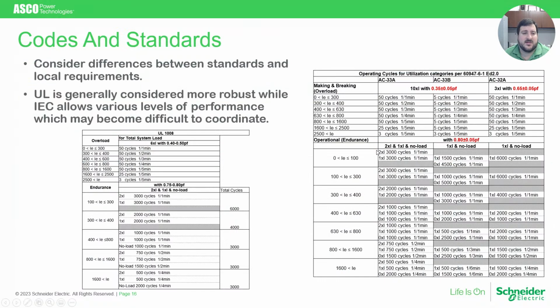But one thing to consider when looking at the difference between the standards is that they are not necessarily apples to apples. They are not necessarily equivalent. It really depends on your needs, as I mentioned. And the UL standard is generally considered a more robust standard, while the IEC standard around transfer switches is sometimes not as robust because it allows various levels of performance, which could become difficult to coordinate and confusing.